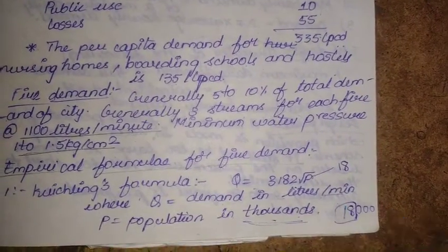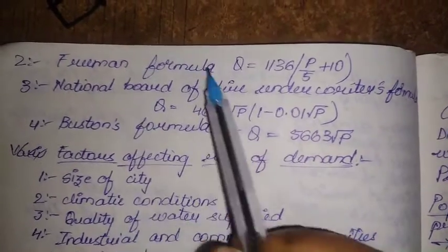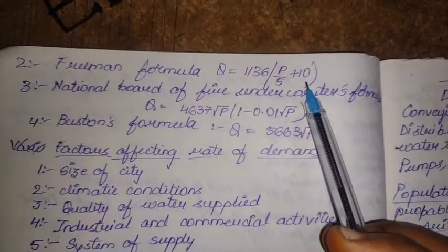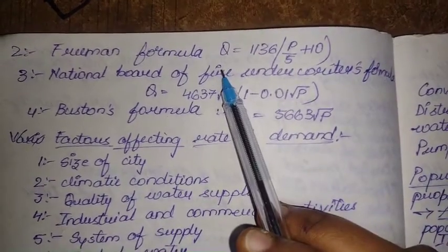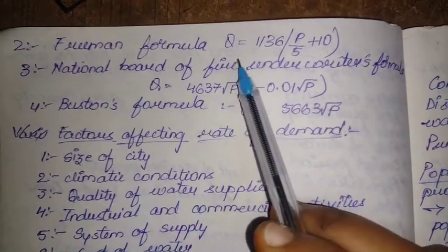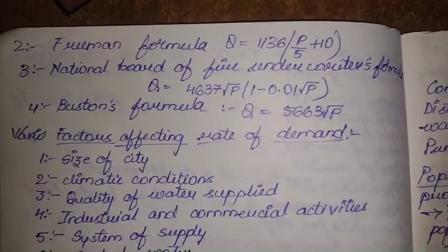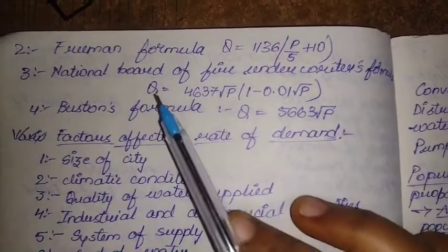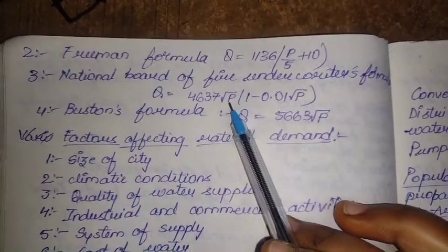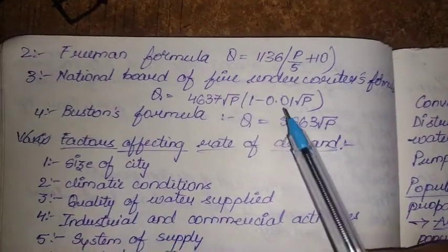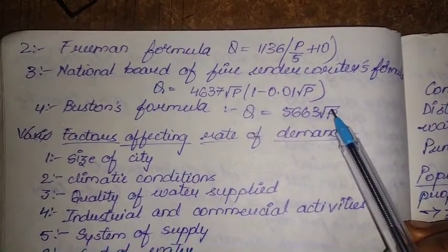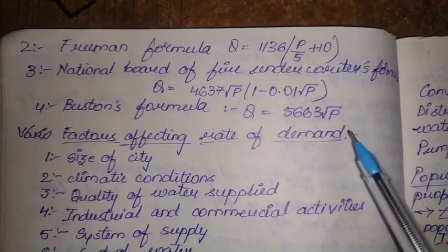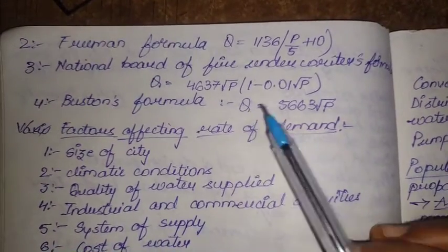The Freeman formula is Q = 1136 × (P/5 + 10), where again P is in thousands and Q is the quantity of water required in liters per minute. The National Board of Fire Underwriters formula is Q = 4637√P × (1 − 0.01√P). Buston's formula is Q = 5663√P. In all these formulas, P is substituted in thousands to get Q in liters per minute.